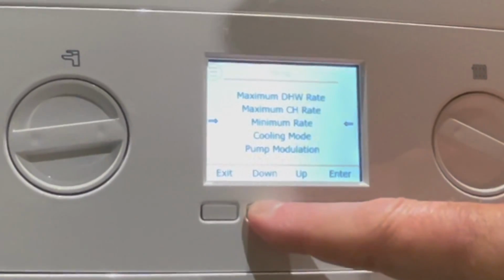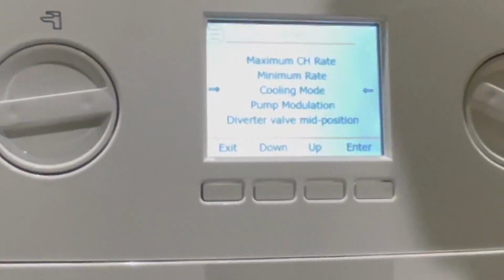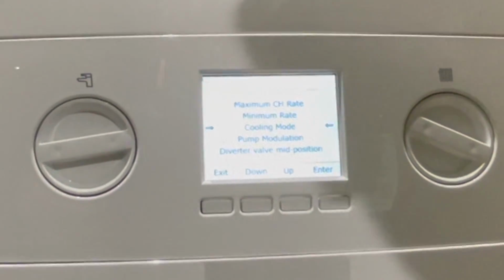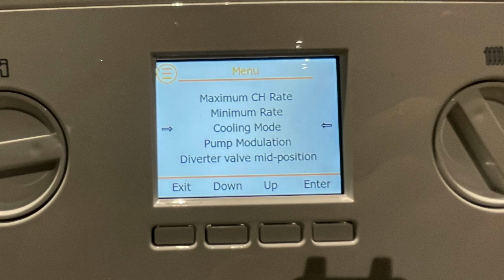Now on the display screen you get everything that you've always got with all the other Ideal boilers, but now you've got a cooling mode. So if you go to service this boiler, you can put it in cooling mode. It will run the fan, it will run the pump, but it won't fire the boiler up, so it will cool it down for you to be able to do your flue gas analysing.